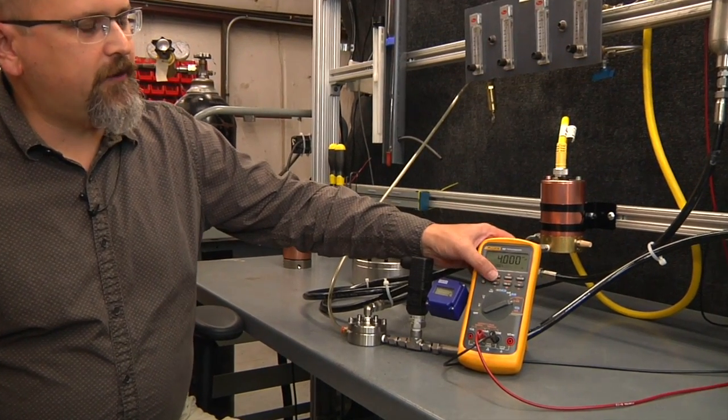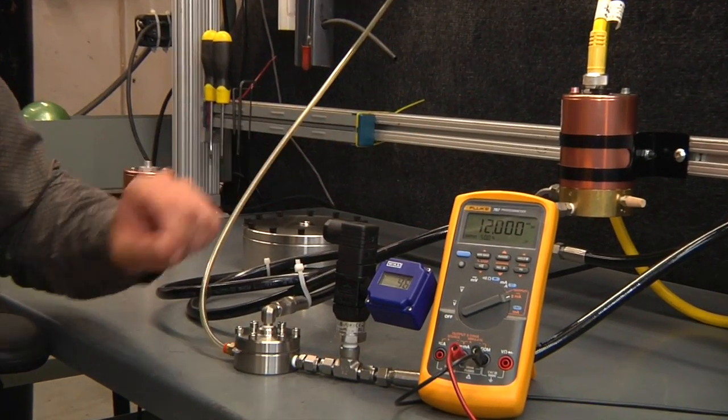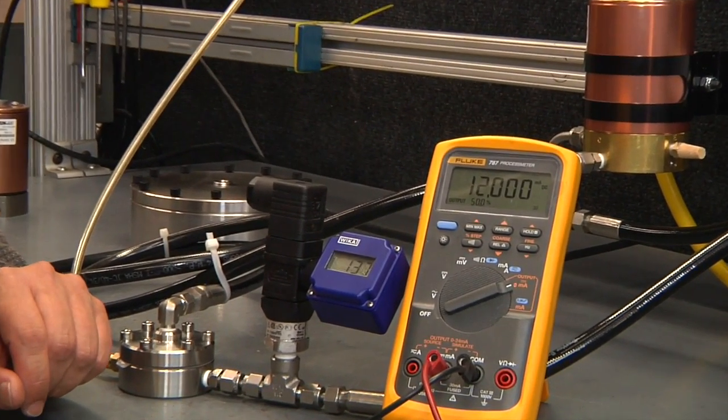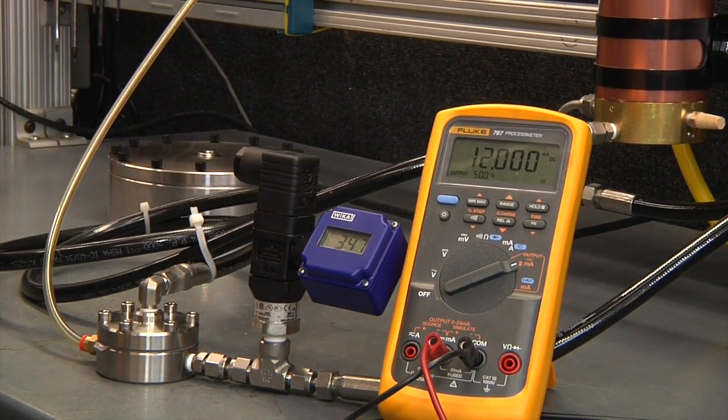I'll go ahead and increase the command signal from 4 milliamps to 12 milliamps. Since that's half scale, we should see the pressure in the system increase to about 500 PSI.